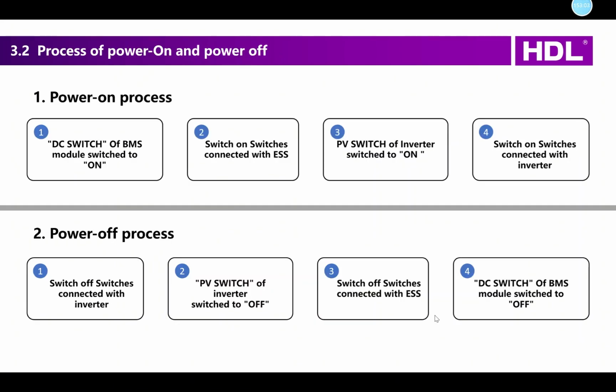Okay, here is the power on and power off process, the right process. So first, if you want to start to power on the system, you first need to switch on the DC switch on the BMS module, not the inverter, and then switch on the breakers or other switches connected with the battery system. After that, switch on the PV switch of the inverter, and then you can switch on the breakers connected between the inverter and the solar panels.